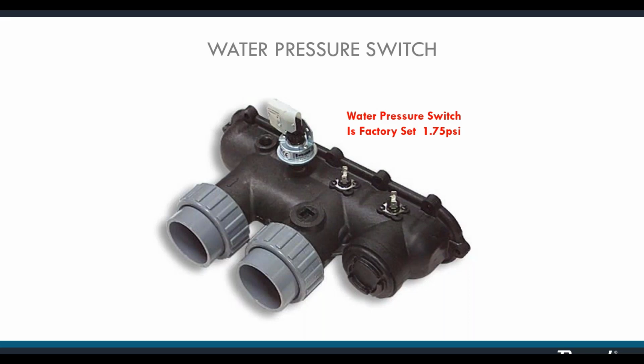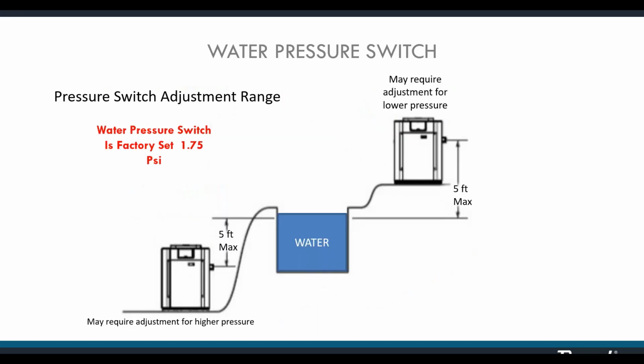This loss of flow causes the pressure switch to open and shuts the heater down. The pressure switch is there to ensure that there is water flowing through the heater. Typically, the heater will operate safely when there's enough flow to generate 1.75 psi. That's where the switch is set at the factory. This, of course, assumes that the heater is installed at or near the water level. Up to about 5 feet above or below the water surface, you can adjust the pressure switch as necessary to require more or less pressure to close.